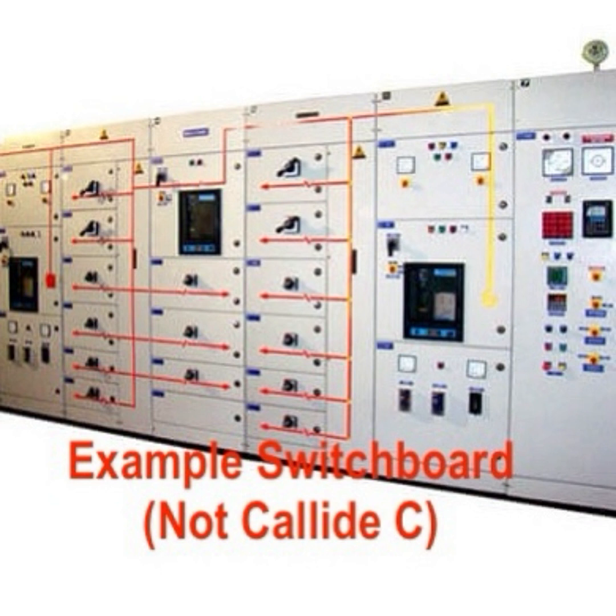The GCB should have reverse power protection to prevent the generator from flipping into motoring mode, like it did in this incident. The fact that CS Energy's report says what it does suggests either A, the report is incorrect in this respect, or B, the GCB had the incorrect reverse power protection settings, even if it was energized. So if the GCB did actually have the correct settings for reverse power flow, then it would have tripped the GCB once the ACS changed over.